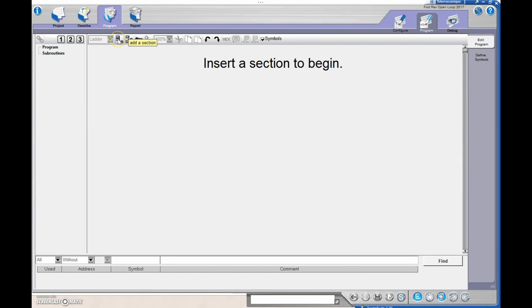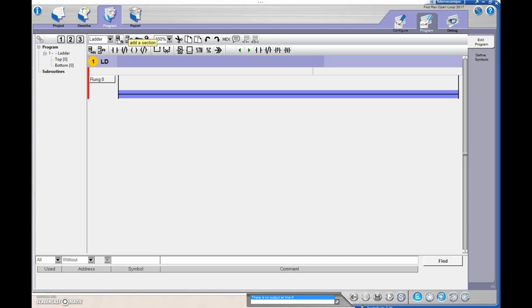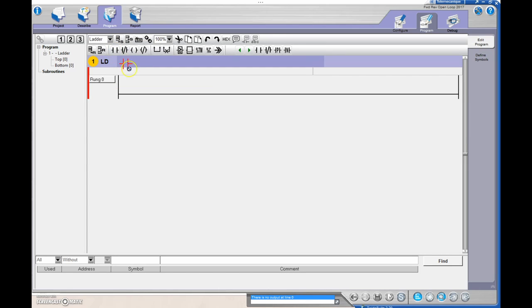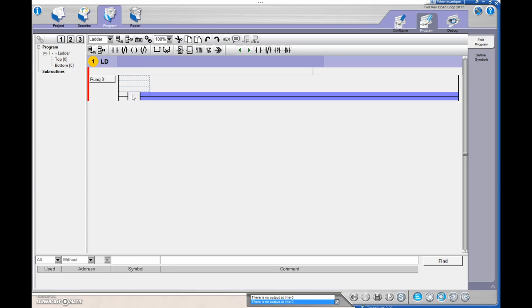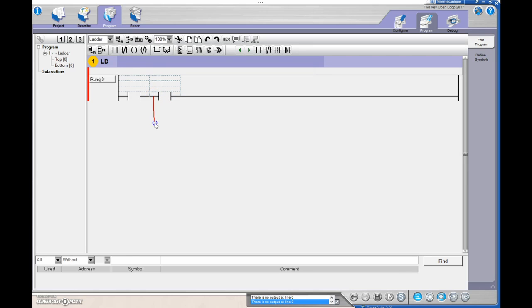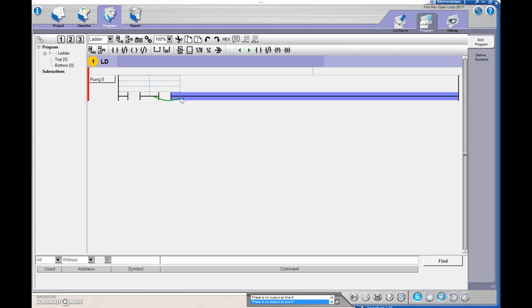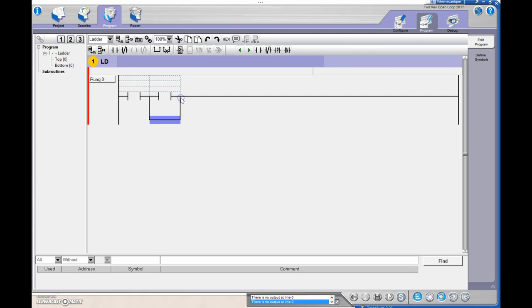Let's drop in a rung. We're going to start off with the stop, then the forward push button. In parallel with that — to make a parallel rung, left-click here, bring the line over until you see green and let it go. That drops in a parallel rung, and I'm going to do an Examine If Closed there as well.